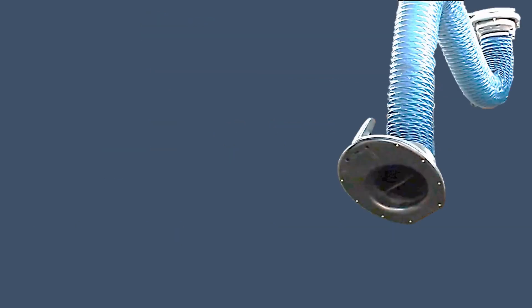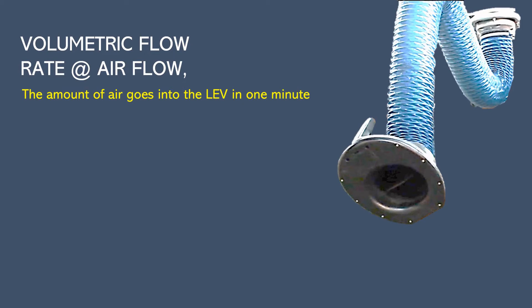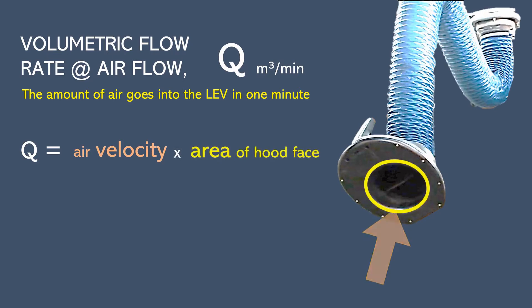Now we are going to learn how to measure the volumetric flow rate of the air that got pulled into the LEV, or what we call the airflow. The airflow is the amount of air that goes into the LEV in a minute. It's denoted by the letter Q, and the unit is cubic meter per minute. To get the airflow, we must measure first how fast the air goes through the hood, which is the velocity, and we multiply it with the area of the hood face or the opening of the hood. To simplify it, we can write it as Q equals V times A.